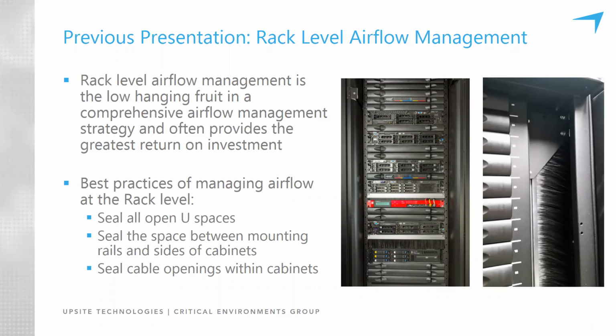But everything within the cabinet, the blanking panels between open spaces and between IT equipment, and sealing the space between the rails and the side of the cabinet are very important for both blocking exhaust recirculation and potentially blocking the loss of bypass airflow, conditioned air flowing through a cabinet where it shouldn't. So that presentation was covered, and those areas were addressed in the last webinar. The third part in this 4-part series will be focused on room level containment best practices. And then the 4th one, coming in June, will be focused on the raised floor best practices.